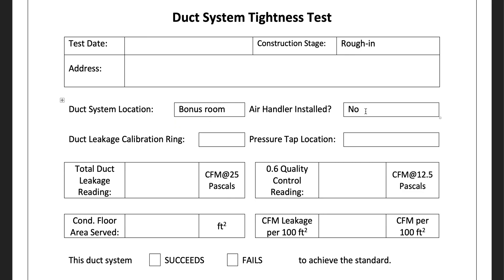If we say no — no air handler installed — then code essentially assumes that 25% of the air leakage you're going to get will come from the cabinet itself of the equipment. So let's say you're in Illinois and your limit is 4 CFM per 100 square feet. If you do the test with the furnace and air handler in place and the system is complete, you're allowed 4 CFM per 100 square feet. If you do it without that equipment — just ducts connecting to nothing with a gap where the furnace will go — then you'd be allowed 3 CFM per 100 square feet. Duct calibration ring: same as before — wide open, ring A, ring B, etc. Let's say you're using ring A.